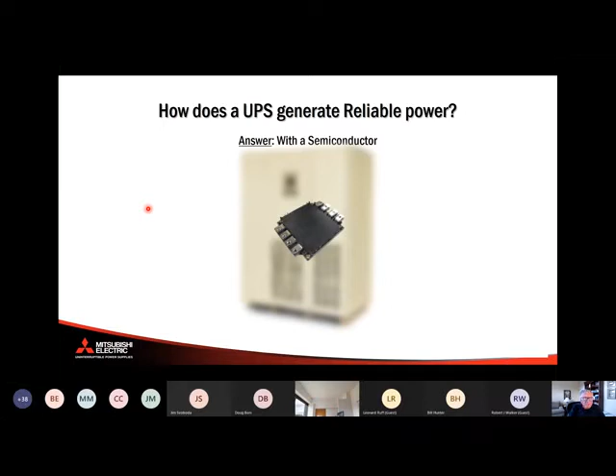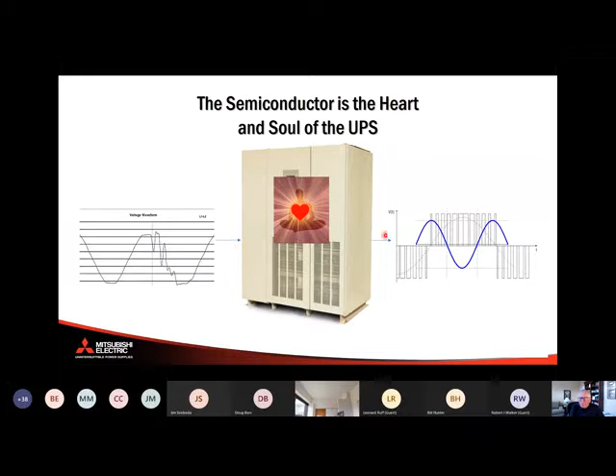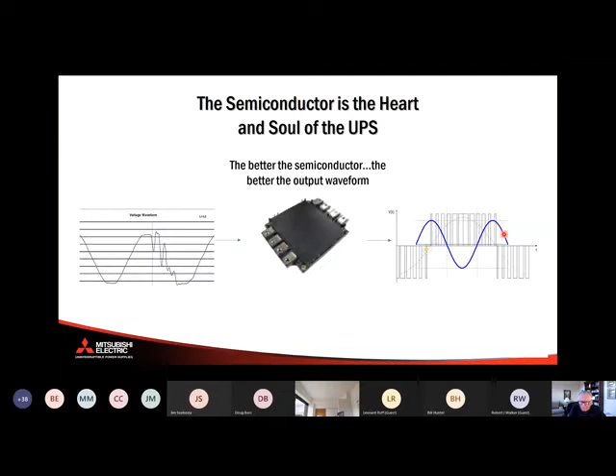By putting semiconductor devices inside. You take AC coming in, convert it to DC, create a DC bus so you can put batteries on. Then you recreate the sine wave with that inverter - go DC to AC, and get the best output possible by using a silicon carbide material instead of silicon. So the better the semiconductor device, the better the output waveform, right?